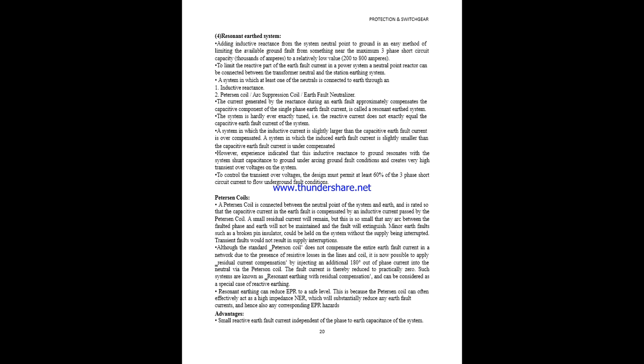Next, considering the resonant earth system, we add an inductive reactance to the line which is connected from the neutral to the ground. The speciality is that it may be considered as an inductive reactance, or we can include a Petersen coil, arc suppression coil or an earth fault neutralizer. So this is regarding its construction.